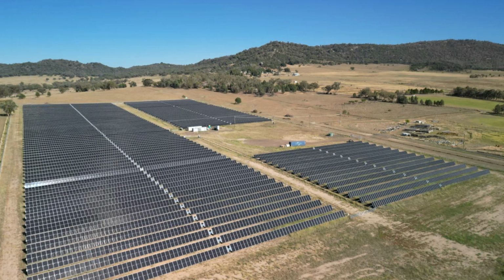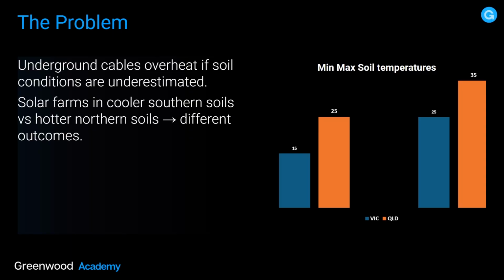Let's get into it. And now here's a picture of one of the solar farms we recently completed in New South Wales, a little under 5 megawatt on the AC side and a little over 5 meg on the DC side. Underground cables overheat if soil conditions are underestimated. Solar farms in cooler southern soils versus hotter northern soils, you're talking about completely different outcomes. Imagine a scenario where you're doing a solar farm in Victoria and you've got soil temperatures ranging from 15 to maybe a max of 25, and you do a particular design. Now imagine if you rinse and repeat and take that same design and go up into the northern states, specifically Queensland, where the soil temperatures can range between 25 and 35 plus degrees. Are you going to get the same kind of cable current carrying capacity? The answer is no, and that's what we're going to be really talking about.